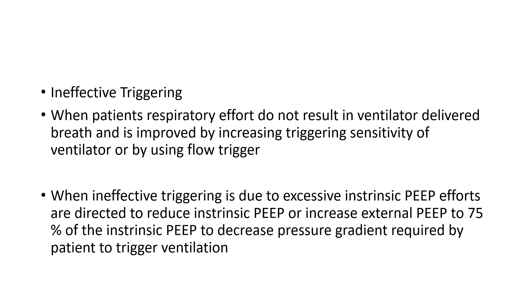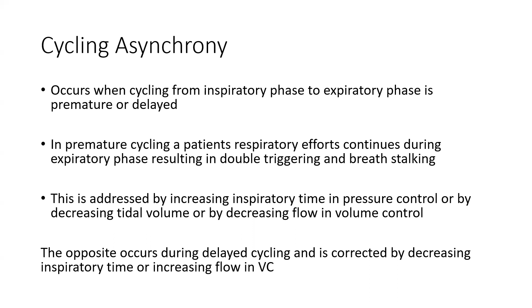Then cycling asynchrony occurs when cycling from the inspiratory phase to the expiratory phase is premature or delayed. In premature cycling, the patient's respiratory effort continues during the expiratory phase, resulting in double triggering and breath stacking. This is addressed by increasing inspiratory time in pressure control, or by decreasing tidal volume or decreasing flow in volume control. The opposite occurs during delayed cycling and is corrected by decreasing inspiratory time and increasing flow in volume control.